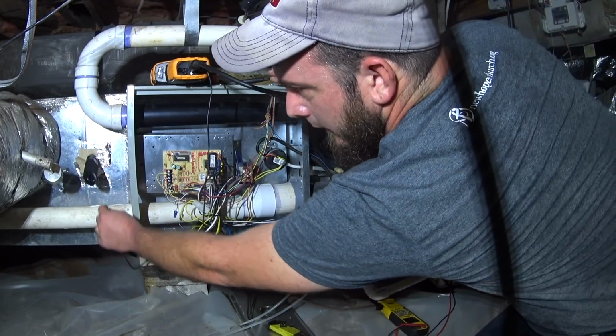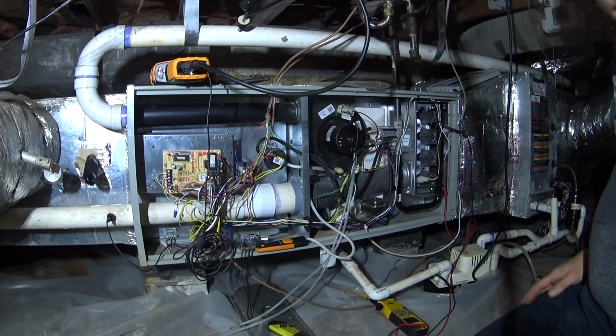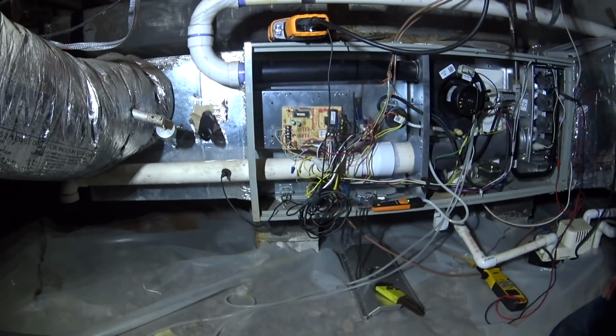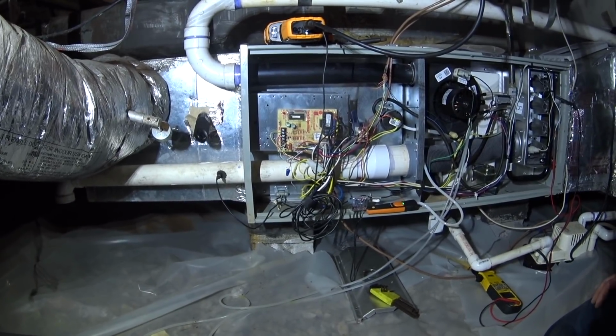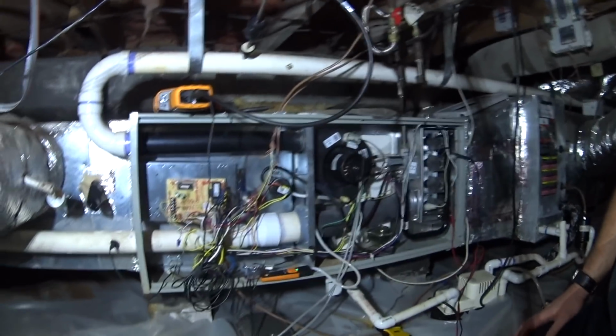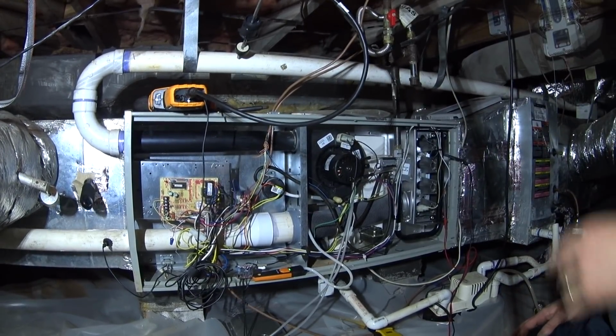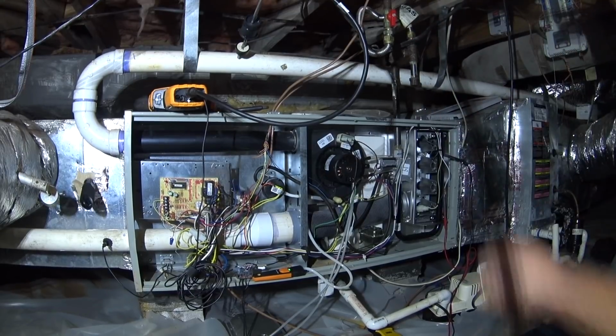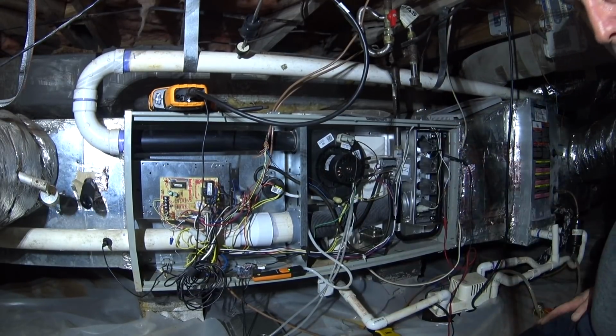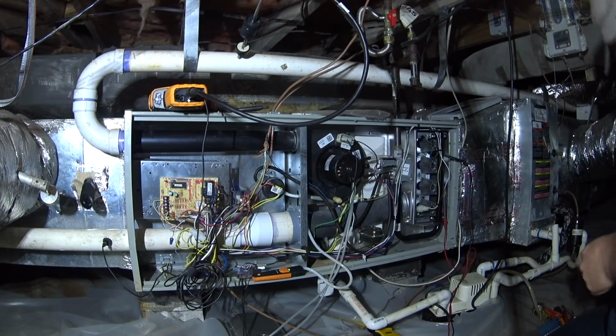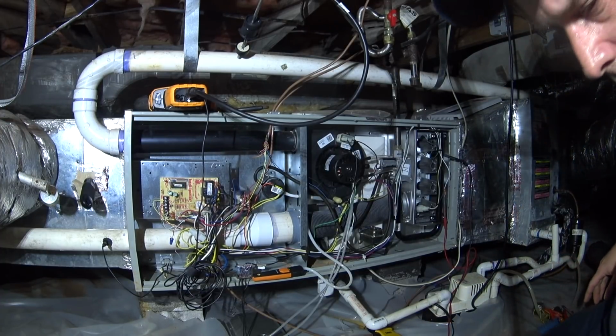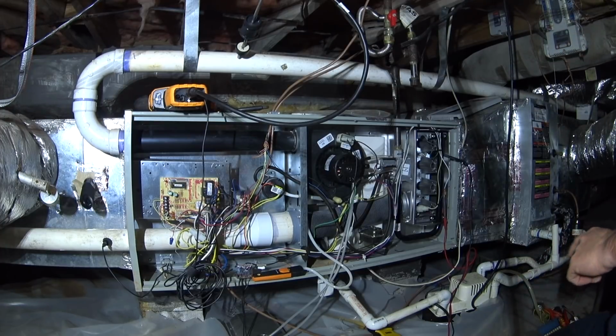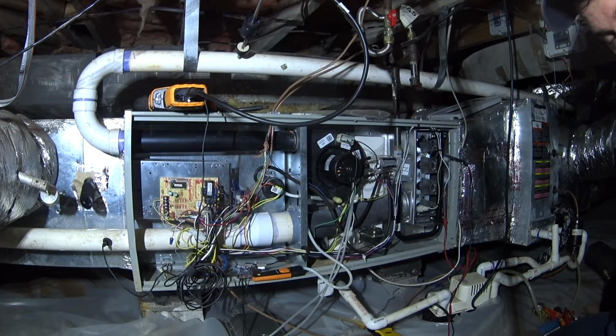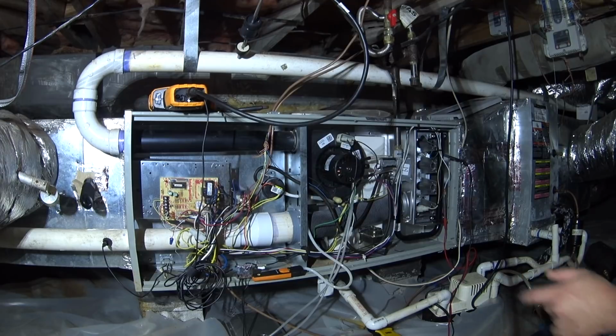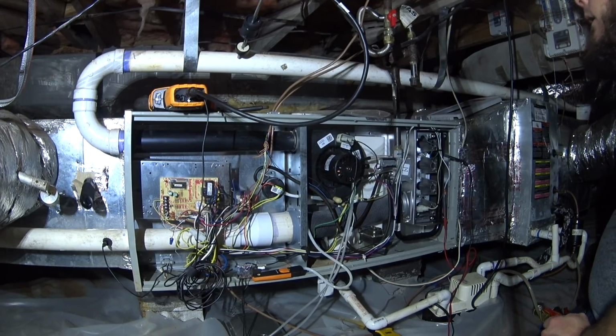We've got a small port here for testing intake air down there on the return side. I guess you could see that already. At this point, we don't have to test combustion air inlet because the combustion pulls from the crawl space. But if we were dealing with a two-pipe system that took both intake and exhaust from outside, or from and to outside, then we'd want to test both.